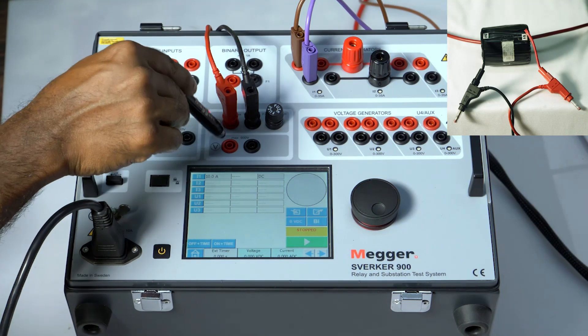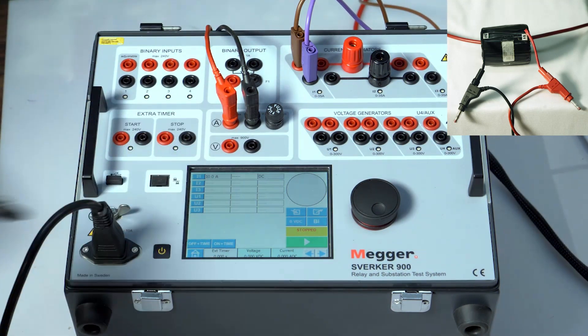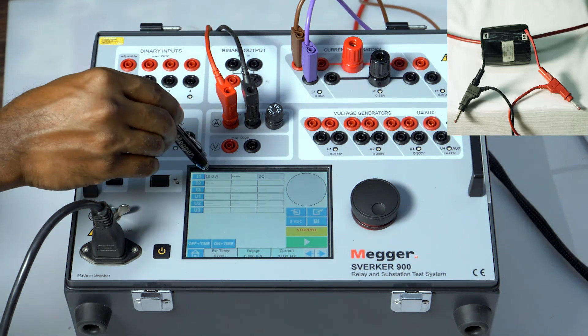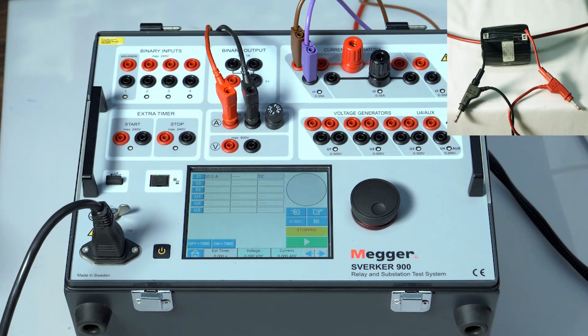Since the voltmeter is not configured, this is not mandatory. Configure 10% of the full load current. We have connected to a 100/1 amp CT, so I have configured 10% of the primary current, that is 10 amps.